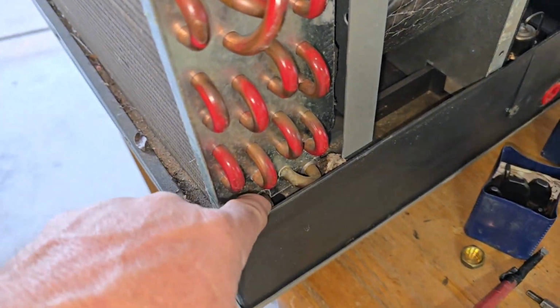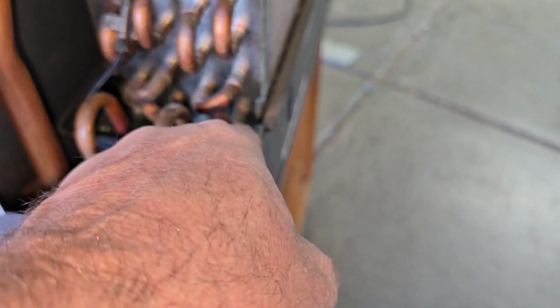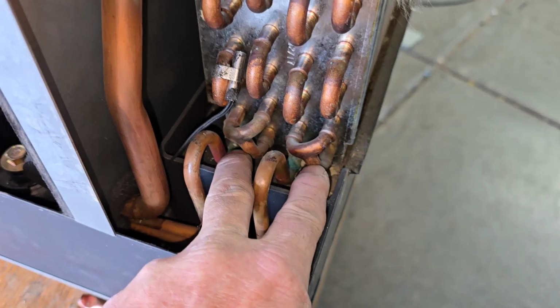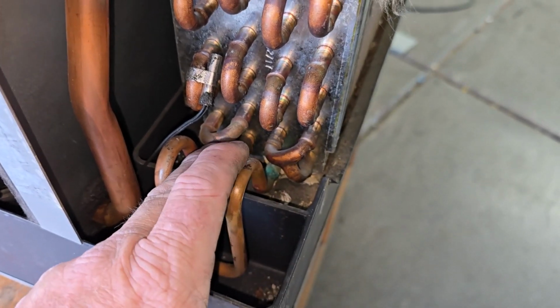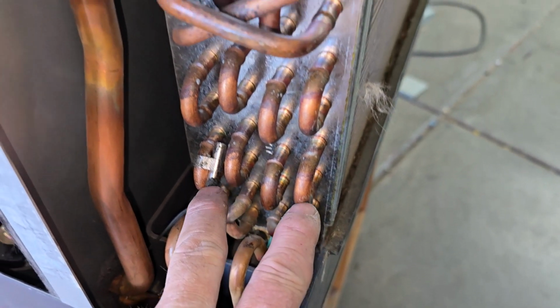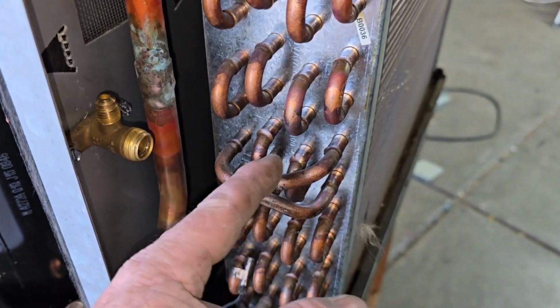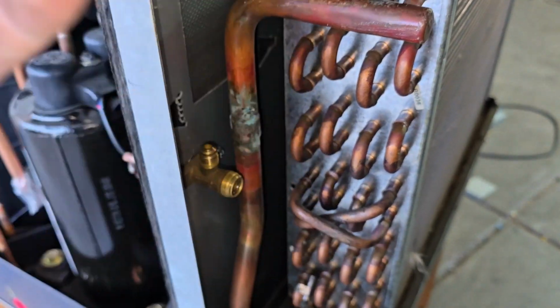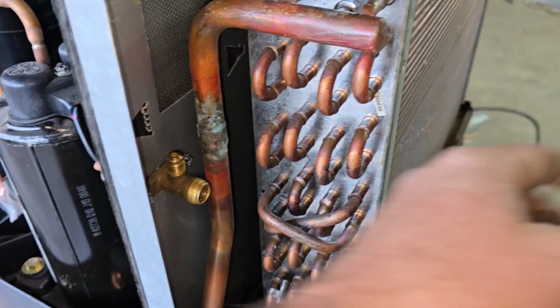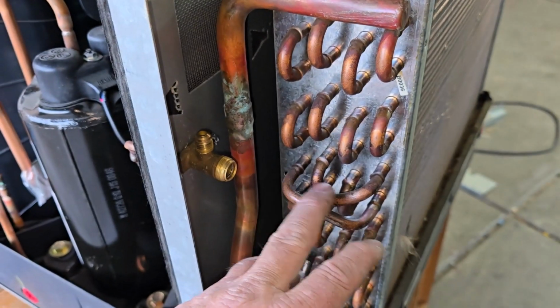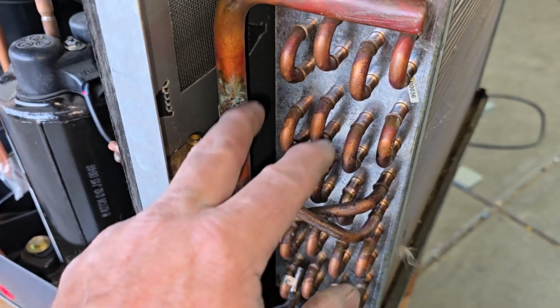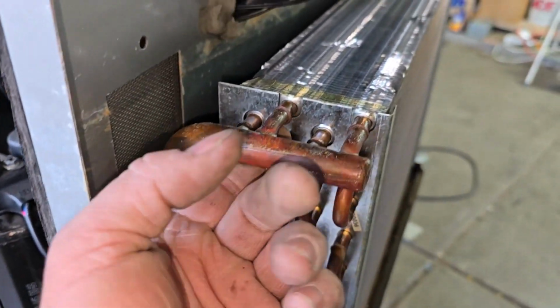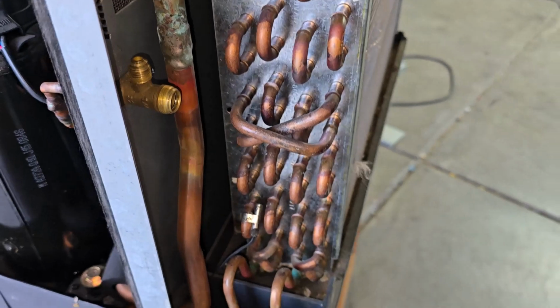So it's going in - yeah, it's just going in, so this line goes in and comes out right here. This one's doing the same thing in parallel. They come out the bottom 2, then hit this U-bend, and split into 4 circuits, just going up as 4 circuits. Crisscrossing again, swapping the side of the coil - you've got your warmest air here, coldest air over here - so they're swapping those 2 of the 4 parallel. Everything else in the middle stays the same, and then they come out as 4 circuits.